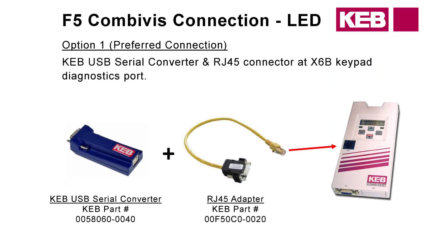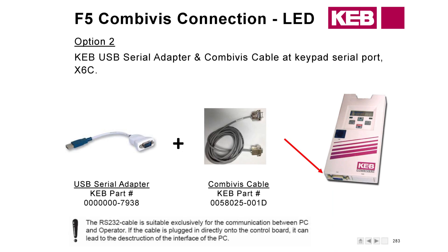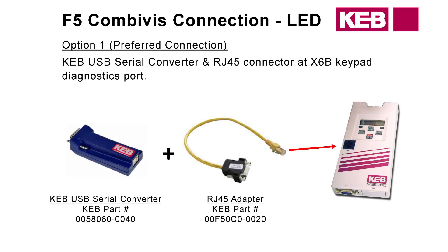If you wish to connect, I'm going to provide you the most simple way. Option one — if you're looking to connect to the older keypad, use the KEB serial converter and the RJ-45 adapter. Not pictured here is a black cable with a USB end that plugs into your computer — when you order the KEB converter, it includes that cable. The other option is to use the Combivis cable plugged into the serial converter, but if you're using serial speed control with your controller, that port is going to be used. So the KEB converter is always going to be available — that's why I prefer it.